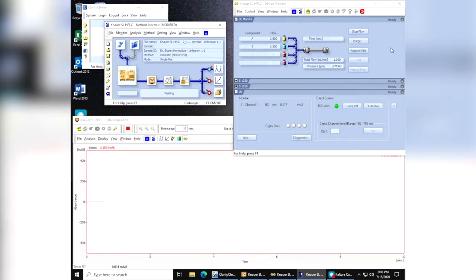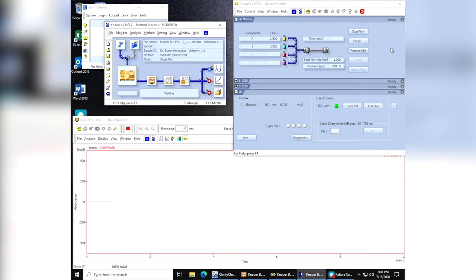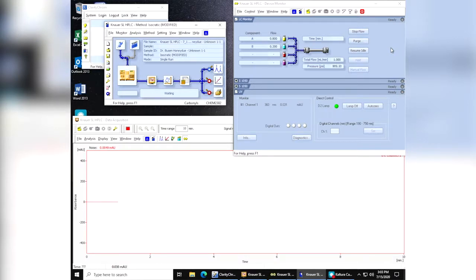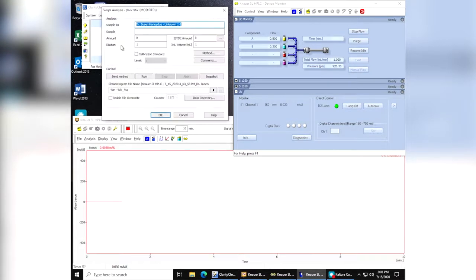The instrument now is showing the 80-20 that we want. The pressure is good now, so it's ready for us to do an injection. But the next thing that we need to do is we'll need to set this up so that we can tell our data file from other data files, because this instrument automatically saves the data once it's collected. So you need to name your file, so you're going to want to go to this symbol up at the top here, the single syringe and sample. You're going to click that.